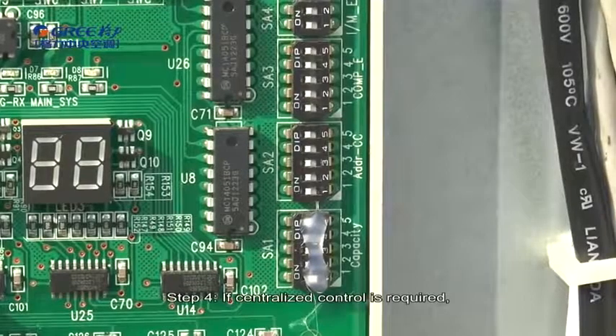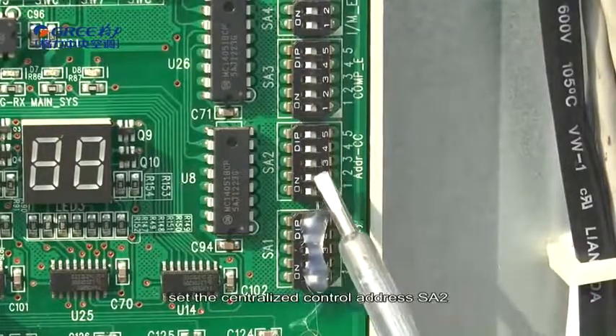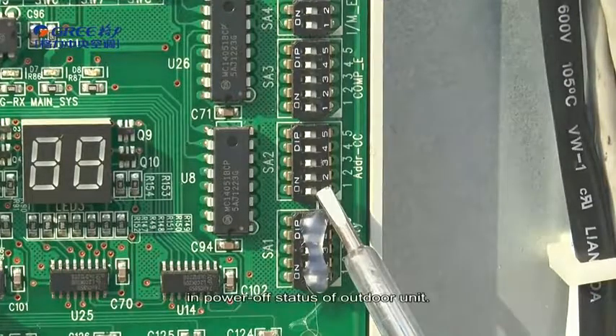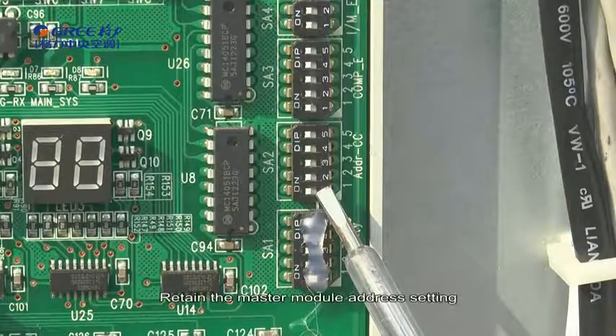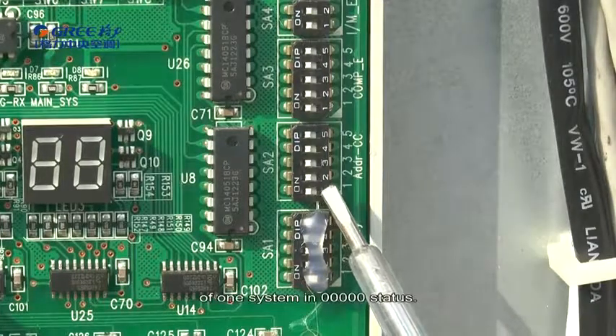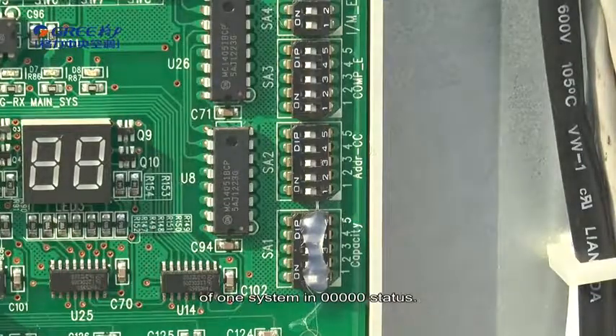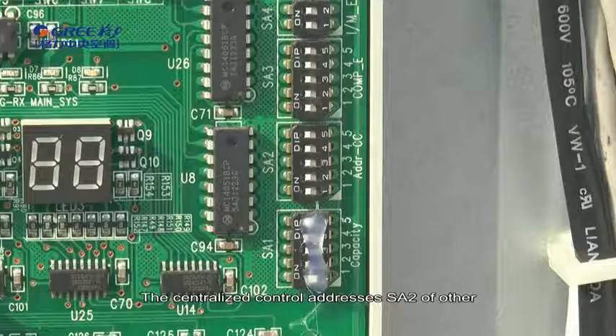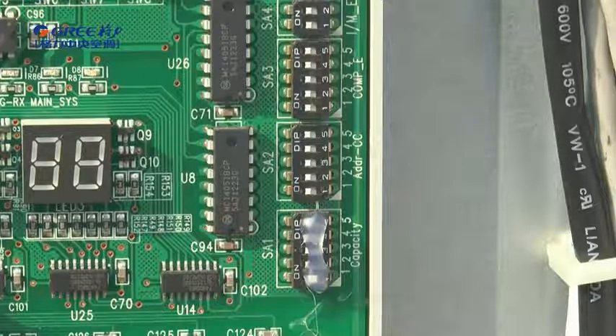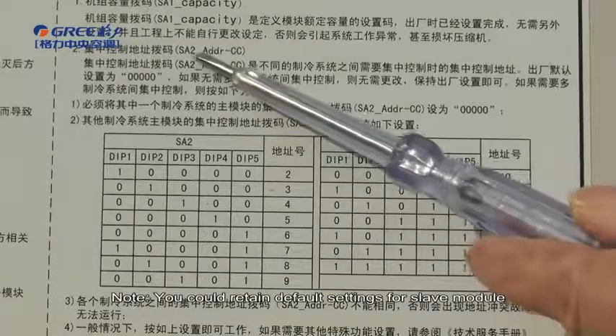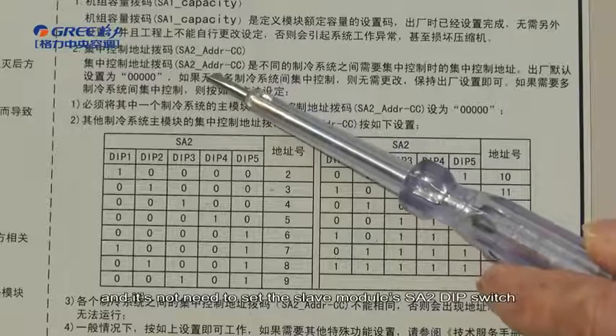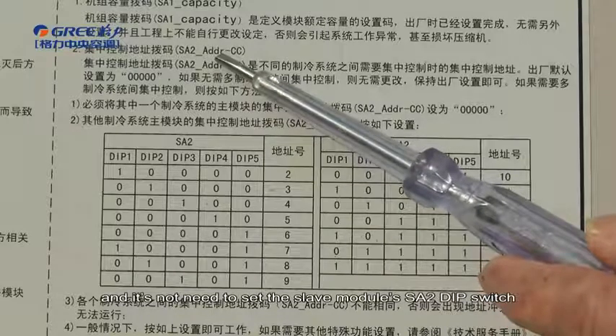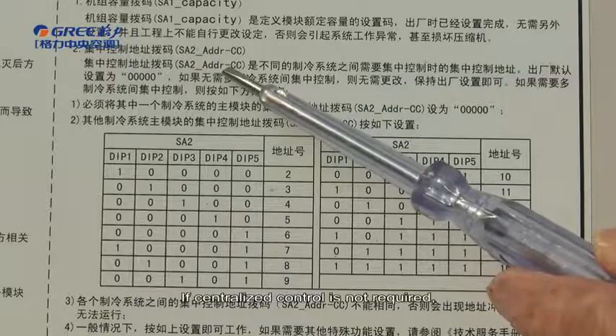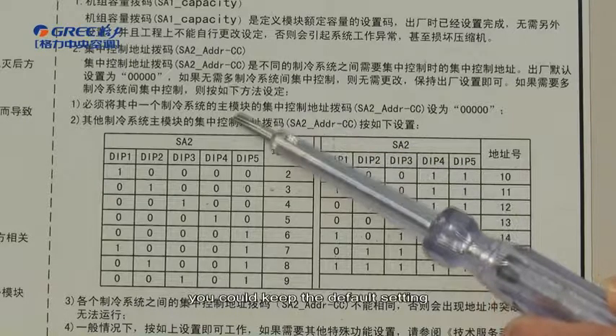Step 4. If centralized control is required, set the centralized control address SA2 in power off status of outdoor unit. Retain the master module address setting of one system in 00000 status. The centralized control addresses SA2 of other systems' master modules cannot repeat. Note, you could retain default settings for slave modules, and it is not needed to set the slave module SA2 dip switches of all systems. If centralized control is not required, you could keep default settings, and it is not needed to set this dip switch.